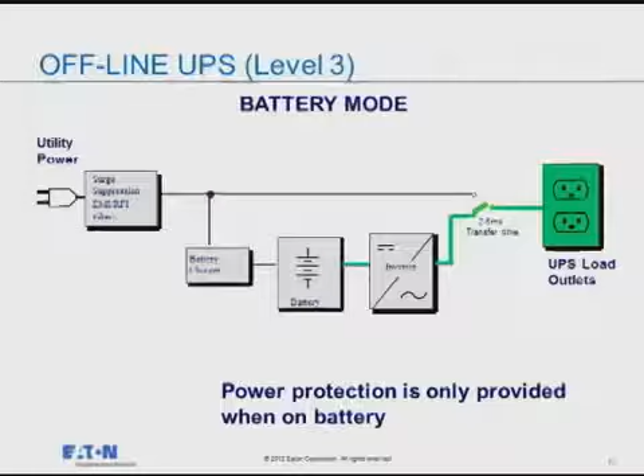With an offline UPS, it's my only means of power quality device, so I'm going to use it every chance I get, and I'm going to take a lot more slices out of it. Typically, an offline level 3 UPS, we're seeing approximately 2 to 3 years life expectancy on the battery, because I'm cutting into it and taking those slices.